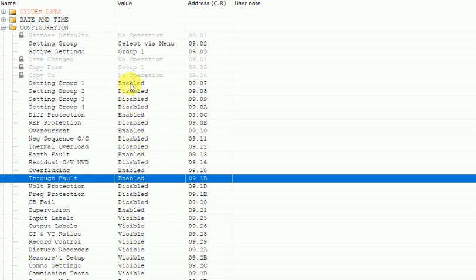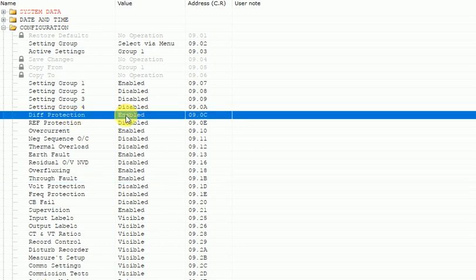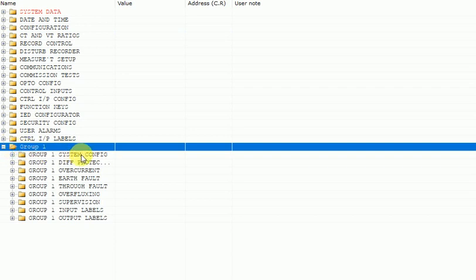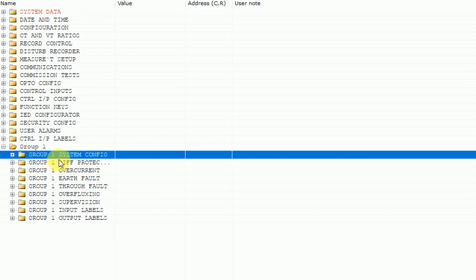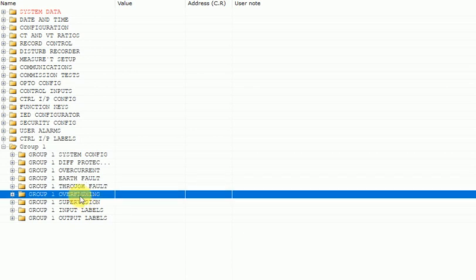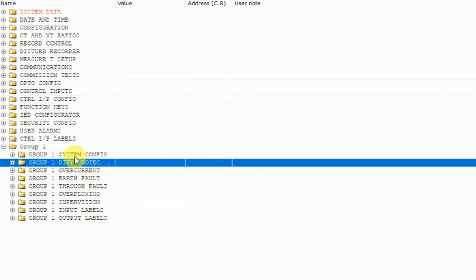We are using this relay for differential protection, so just enable the differential protection part. I will discuss only the differential protection. After making differential protection enabled, at the bottom under Group 1 you can see two important parameters: system configuration and the differential protection settings. These two are very important for differential protection of a transformer or reactor.